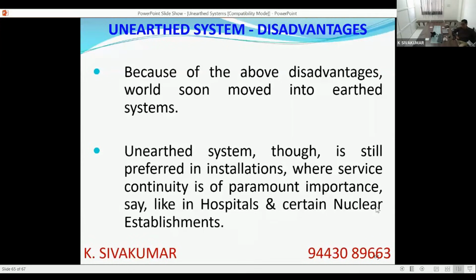Unearthed system, yes, there are certain installations where service continuity is of paramount importance, say in hospitals, where operation theaters or critical diagnostic equipment are there. They don't want power interruption during a surgery or during a diagnostic where the results may be tilted. So for locations where service continuity is important, people still go for unearthed system. In such cases, the network itself is split with separate transformers. One transformer with earthed system for the normal system, and one transformer with isolated neutral for special areas like hospitals, operation theaters, diagnostic rooms, and certain nuclear establishments also. They want unearthed system. They don't want supply continuity to be disrupted. So unearthed systems are now confined to very minimal locations.